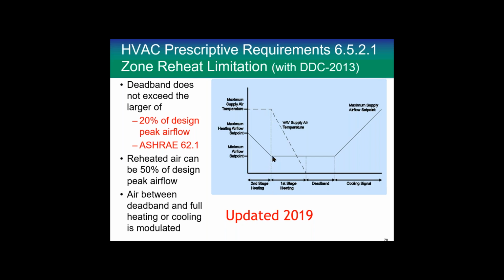And then the second stage of heat, in case that's not enough, we let you open the damper back up. So the damper would open back up until you were putting a maximum of 50% of the airflow that you had over here through. So again, this is this kind of modulation where we're hitting 20% at the low, but we're allowed to go up to 50 over here. And then sometimes that would need a little more cooling, so we go this direction. Anyway, so that's the way that works.